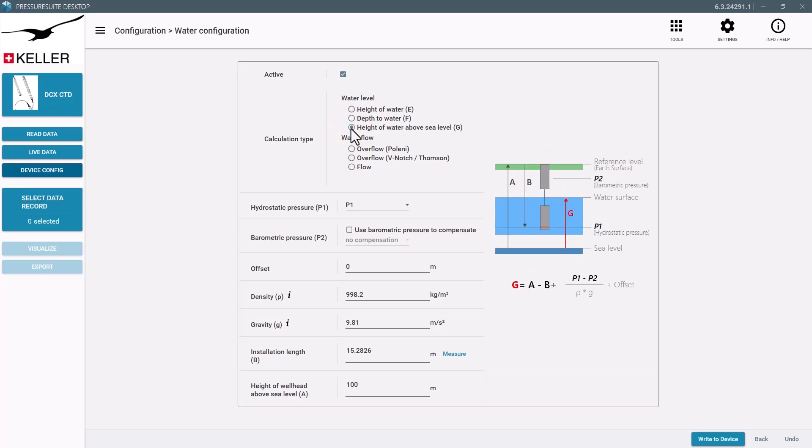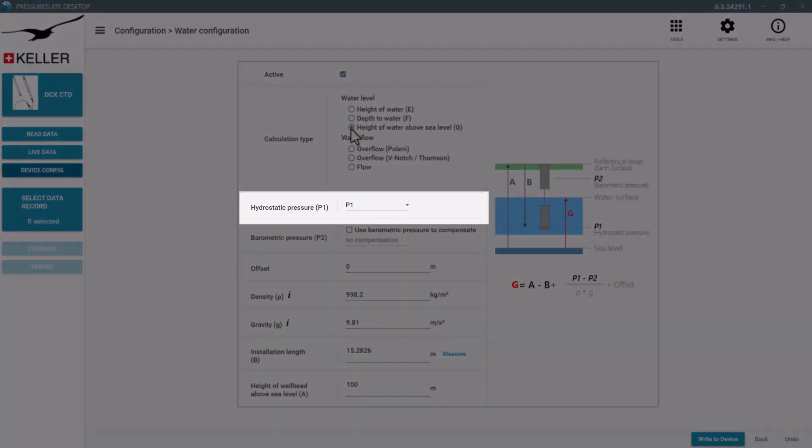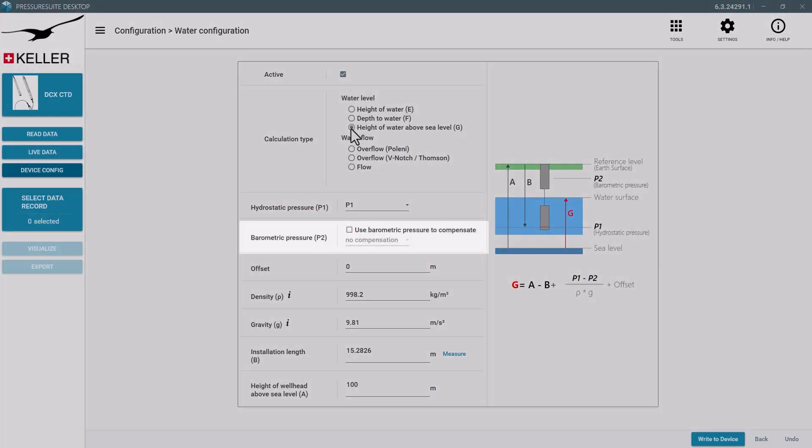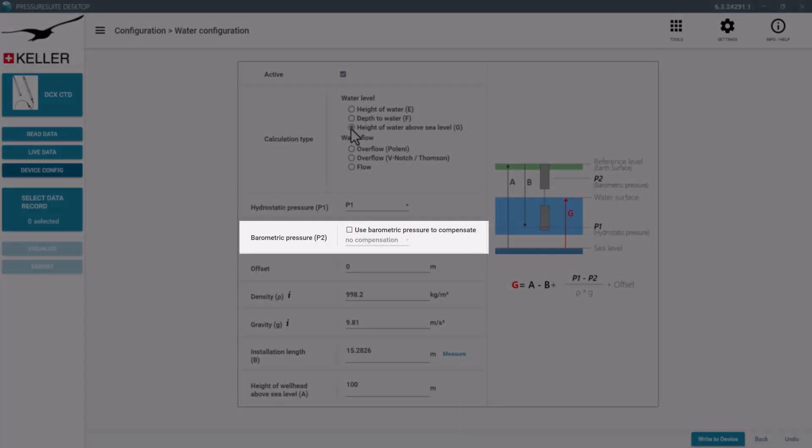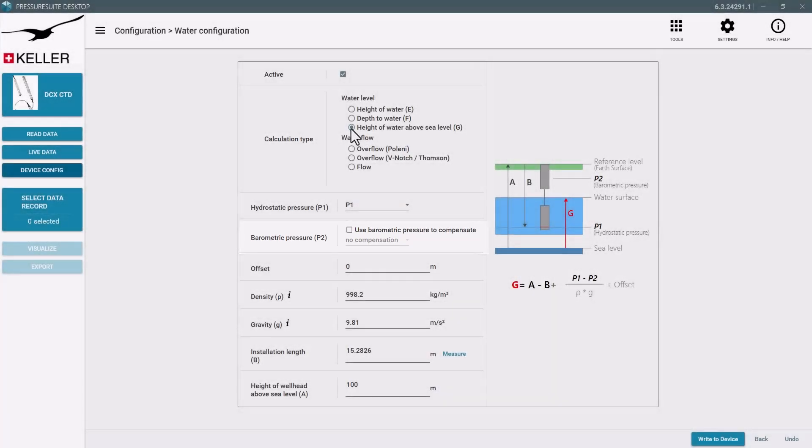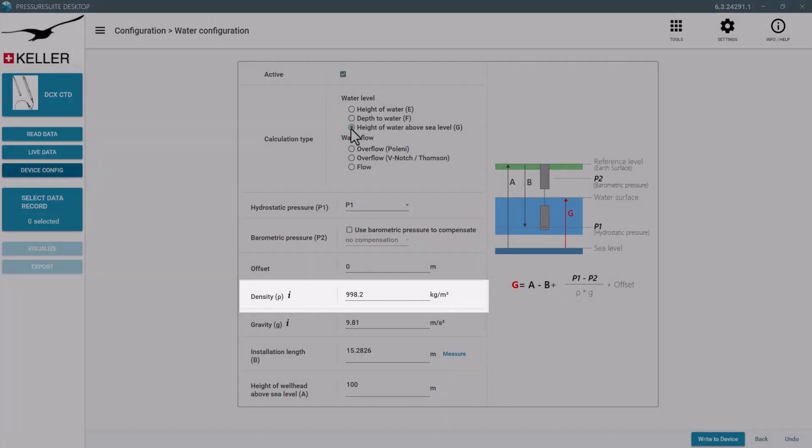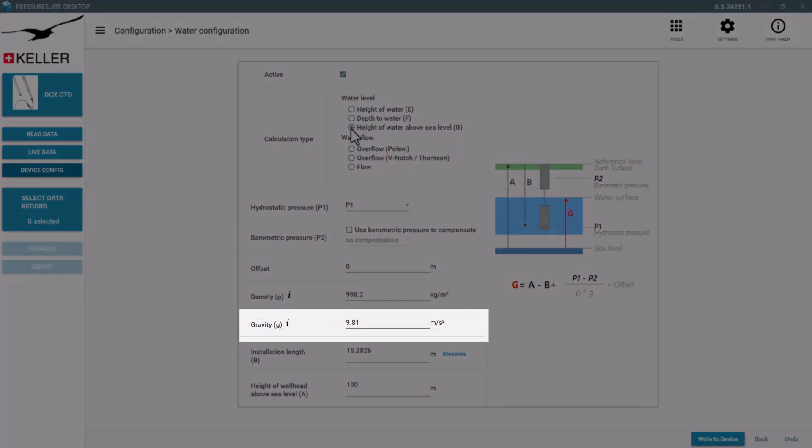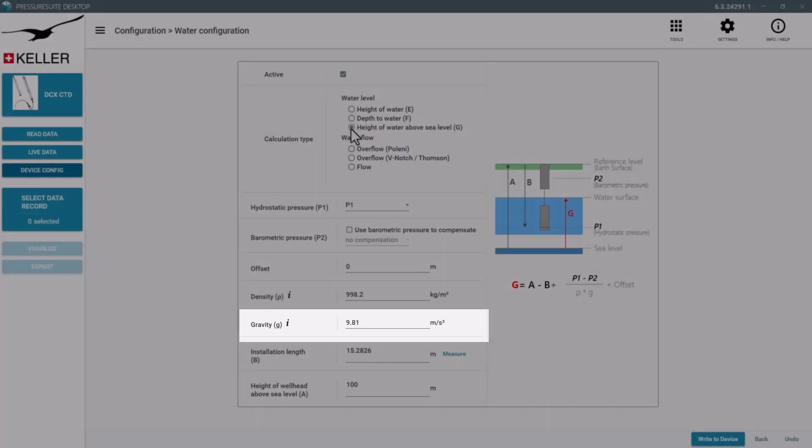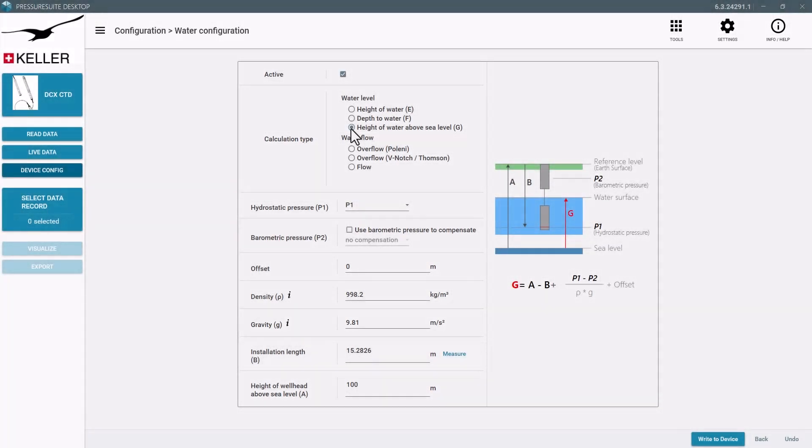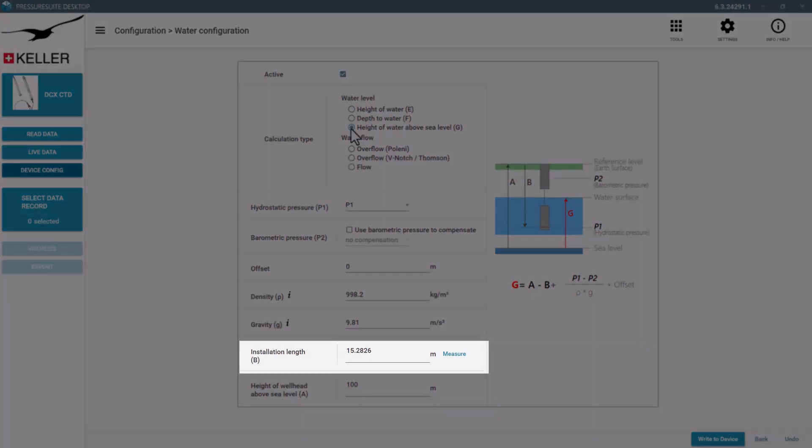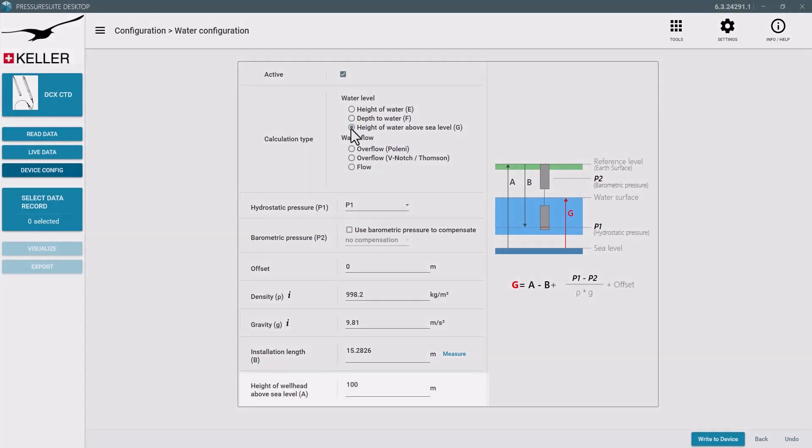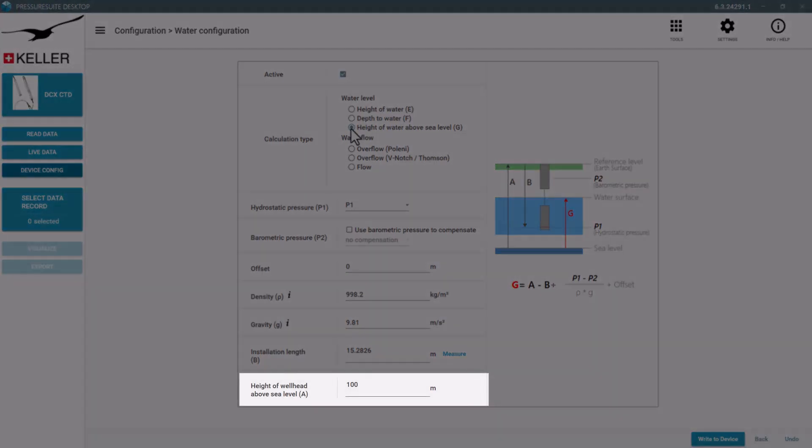For the formula we need the hydrostatic pressure, the barometric pressure, the density, the gravity, the installation length from the top of the wellhead to the bottom of the sensor, and the wellhead height above sea level.